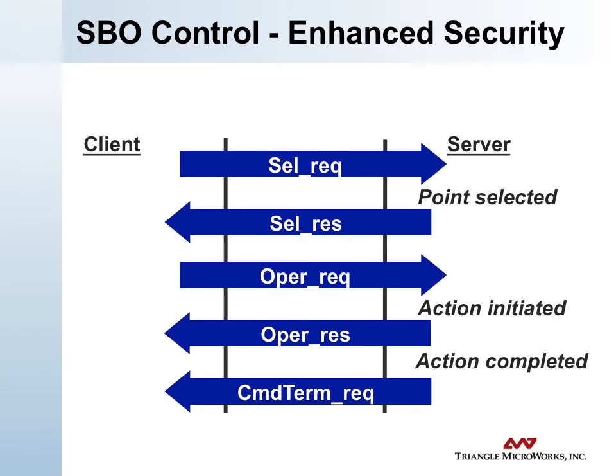Select before operate control with enhanced security closes that feedback loop. It is again a two-step process — selection and response, then an operate request and a response that the action has been initiated — but after that, a command termination is returned from the server to the client confirming the action is completed. The mental model for this is contact closure: the operate request begins the contacts moving, but the command termination signals when they have completed and are stable again.